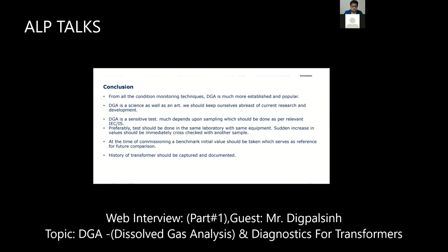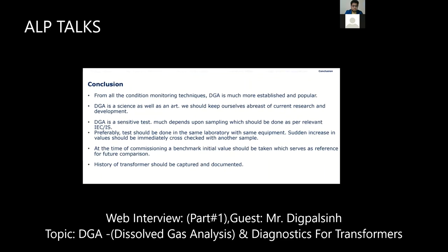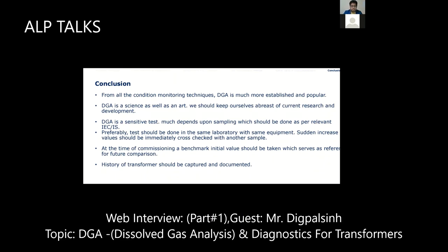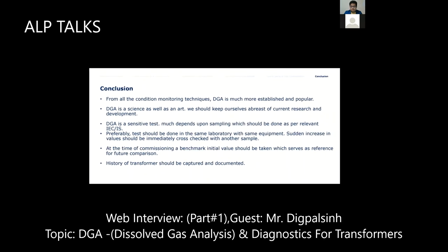And the history of the transformer should be captured and documented. If you find acetylene in your transformer, in that case you have to check the loading cycle of the transformer. If the customer has overloaded the transformer, it is a commercial matter. If it is in the guarantee period and some gases have come inside the transformer, the customer asks us, my transformer is under guarantee and still, within 1 year, it is showing acetylene. In some cases our transformer is healthy but the operator has overloaded it beyond our nameplate. It is the customer who loaded it beyond its limit, so obviously its temperature will increase and acetylene will be formed inside the mineral oil. So to cross-check, the history of the transformer should always be captured.